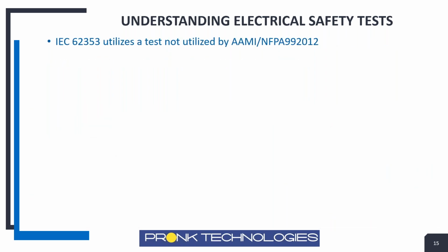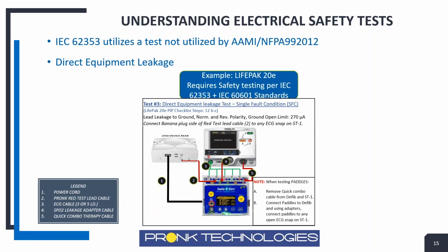But they ask for a third test that's a little bit unique. It's more commonly being utilized in the US now, and in service manuals you'll see it. It's the IEC 62353 standard. It requires a direct equipment leakage test, which NFPA doesn't do and 60601 doesn't do. This is an IEC 62353 standard. It says, I want you to do a kind of complete leakage test, a direct equipment leakage test for everything connected to the device at once.